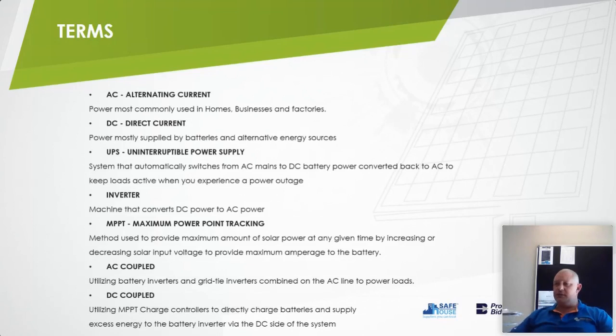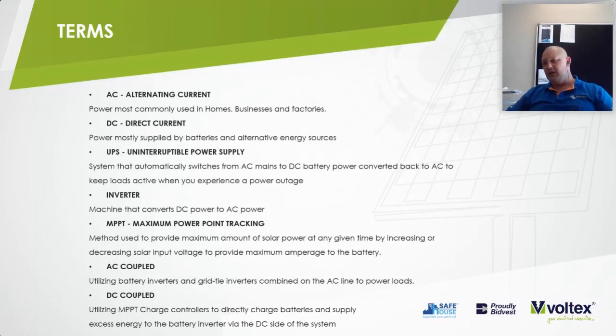UPS is a system that automatically switches from mains to DC power, converted back to mains, to power your loads in the event of a power outage. An inverter is a machine that converts the DC power, battery power, to AC. MPPT, maximum power point tracking, is a method used to provide the maximum amount of solar power available at any given time. AC coupled is utilizing battery inverters and grid tie inverters combined to power your loads and charge batteries. DC coupled is using an MPPT charge controller to charge your batteries directly and utilize excess load via the DC side of the system, called the DC bus, to power loads as well.